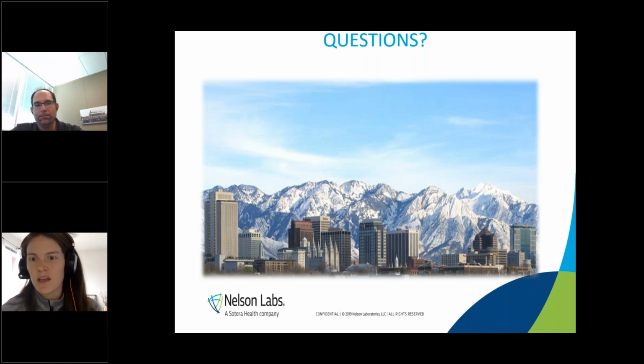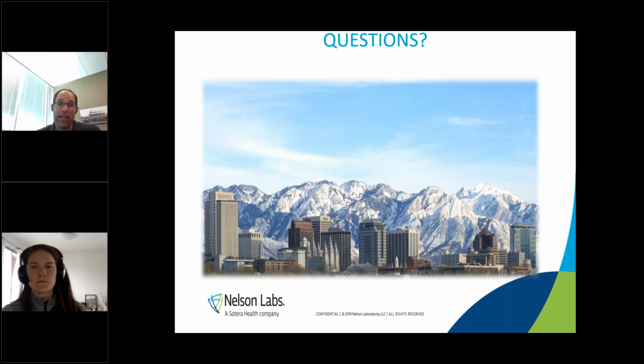Yep. Thank you. You mentioned the regulatory trend is to use chemical characterization data in lieu of certain endpoint testing if appropriate. This person, Stephen, has heard that typically chemical characterization is not accepted for cytotox, sensitization, and irritation. Why is that? Yeah, so you're right. Right now, if you look at the standard, the new 10993-18, it talks specifically about the endpoints, and not only that, the FDA guidance document also calls it out, right? So it talks about what endpoints you can use chemistry for and which ones you can't. And specifically, cytotox, sensitization, and irritation are not listed there.